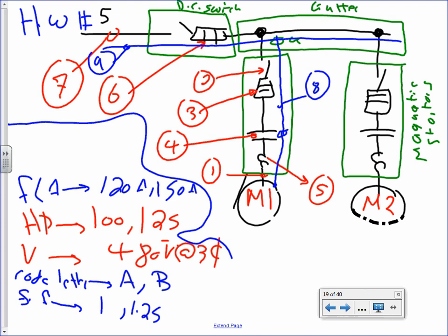When you do Revit, I know we're not doing it yet, but as we start laying out our power and circuiting them, it will be great to do the calculation right away and plug in your overcurrent protection device and your conductor size, because it will be populated by the schedule. If you did not, no problem. Your schedule is just going to be wrong, and you have to adjust it right at the schedule. Okay? So this example, Jeff, was a quick review of what we have done.